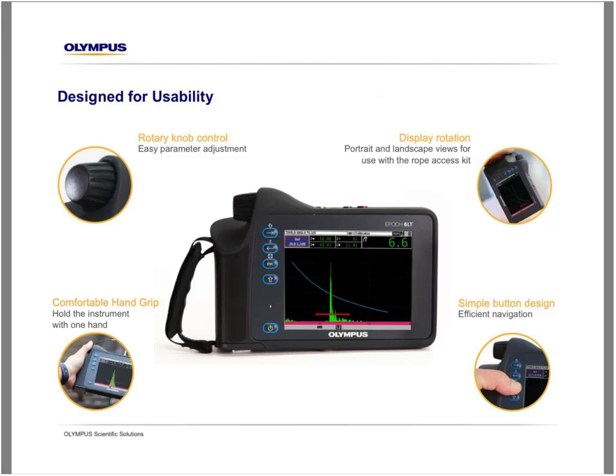In terms of just the basic ruggedness and usability of the EPOCH 6LT flaw detector, the instrument does feature a rotary knob control. So for parameter adjustment, for value slewing, this is a very traditional and very easy way to manipulate the instrument once you're highlighted on a parameter.